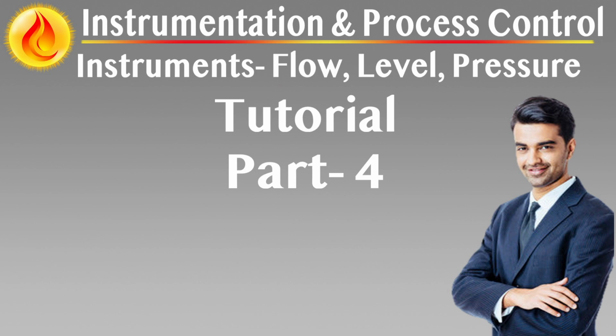conditions. Turbine flow meters for high accuracy volumetric measurement in clean liquid and gas services. Turbine flow meters offer a precise and repeatable method for measuring volumetric flow of clean, low viscosity fluids, particularly where high accuracy, fast response, and pulse output are required. They operate by translating the velocity of flowing fluid into rotational speed of a bladed rotor. The resulting signal is proportional to volumetric flow rate. This makes turbine meters especially well suited for custody transfer, fuel dispensing, blending, and utility monitoring, provided the fluid is free from contaminants and pressure remains stable.